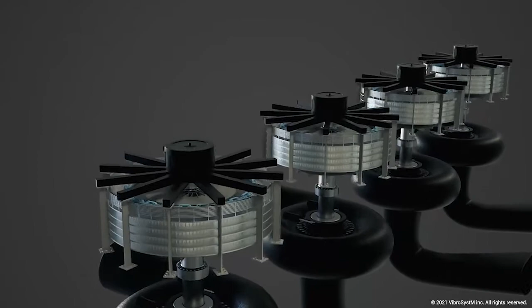VibroSystM's air gap monitoring system, commonly known as AGMS, helped the utility and the OEM solve these issues and prevent any damages. As testified by the customer, the repairs and verification using the AGMS saved significant time and costs. The new method should be adopted in the future since it detects problems before the commercial operation of the units.